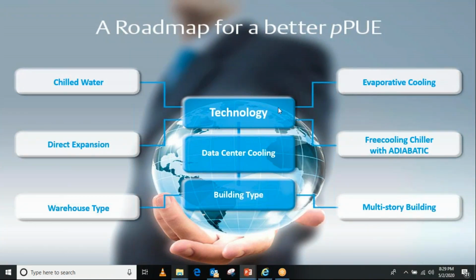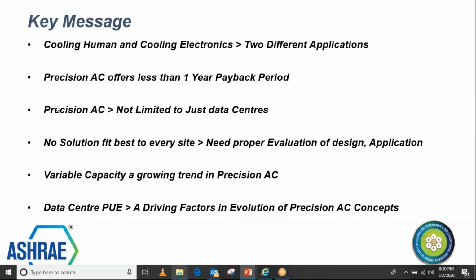There is a lot of change happening in Precision AC, from a typical system going towards evaporative, adiabatic, high chilled water, high DX return temperature, and different types of buildings, with multi-story and warehouse-type data centers coming. And I'm on the last slide now. The key message here is that there is obviously a difference. These are two different applications: cooling humans, comfort, and cooling electronics or machines are different. So the cooling systems should also be designed differently. And the ROI for Precision AC is much more attractive. We must adopt these kinds of cooling approaches wherever we have to cool machines.